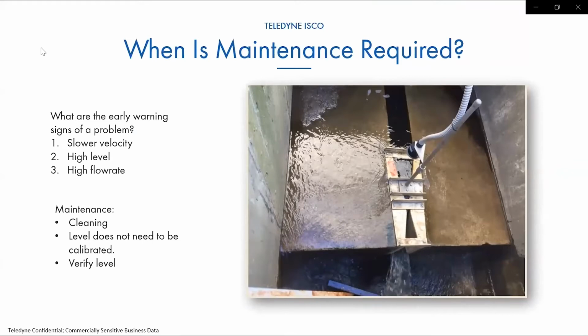If you had an AV sensor upstream of this application, that would be another way to actually continue to get accurate flow readings. This flume right here, your flow rates are obviously incorrect because it's reading the water depth of a full flume and calculating off that water depth when actually we only have a couple inches of water going through there. But an AV sensor would read the water depth and the slower velocity and continue to give you proper flow rates.